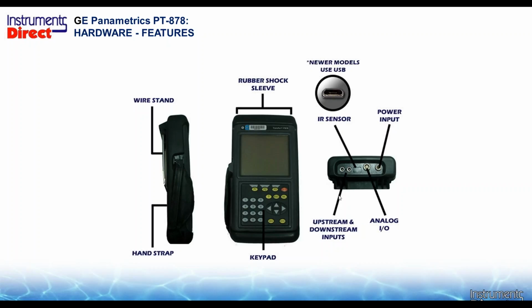Depending on the vintage that you have, the older devices have an IR sensor for communications, and in the last year or so, the newer models have a USB port. There's a sensor across the top, so we can have a little bit better interface there. In addition to that, you can have an analog port, and here are the ports to put the upstream and downstream clamp-on sensors.